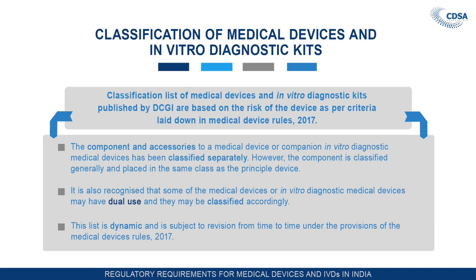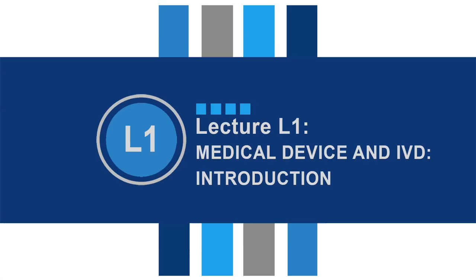Under the classification list, each device is assigned a general intended use as guidance for applicants intending to apply for import or manufacture of medical devices and in vitro diagnostics. The classification list is dynamic and subject to revision by the Central Licensing Authority. Based on the classification, applicants submit applications to the Central Licensing Authority, and specific technical requirements and fees corresponding to the risk class of the medical device are prescribed in the Medical Device Rules 2017.